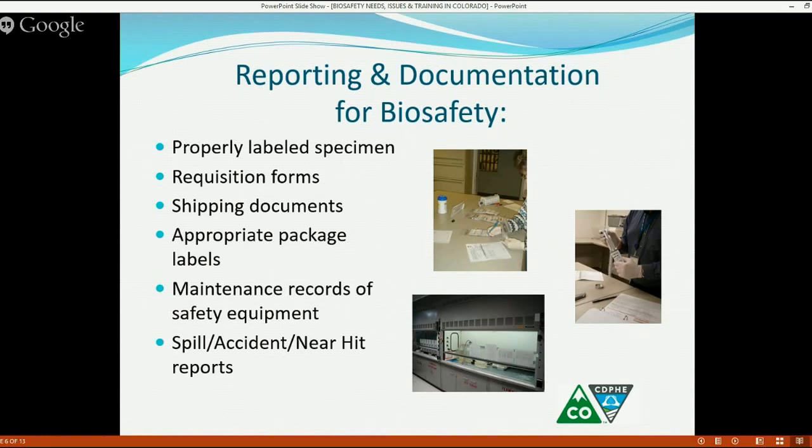We also heard this morning, keep the maintenance records of your safety equipment, not only your biosafety cabinets and chemical fume hoods, but your cappers. Be sure you have batteries and everything that you check, be sure they're working properly. We've had problems at CDC in their labs where, when they're working in BSL-4s, some of their space suits had leaks. We don't go to that extent, but be sure the things that you have work, that you have the proper items there.